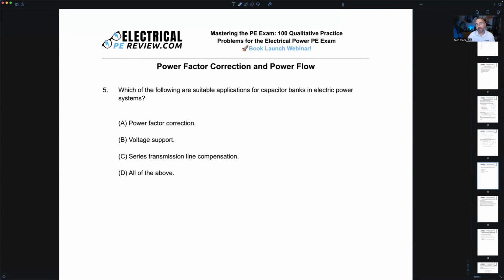Yeah, anytime I see capacitors, their number one application in power systems is for power factor correction, right? Power factor correction is one of the subjects on the PE exam. Good, I'm seeing a lot of D's. I'm seeing a lot of all that applies. All right, what do we think? First of all, everyone knows what power factor correction is, right? Most common application of capacitors. We use them to supply reactive power to improve the power factor of the system. Most common use case of that is induction motors, heavy lagging loads. Instead of supplying the reactive power that the induction motors need from the power supply from the utility, we can install capacitors that act like a reactive power supply. And the whole point is to save money, right?